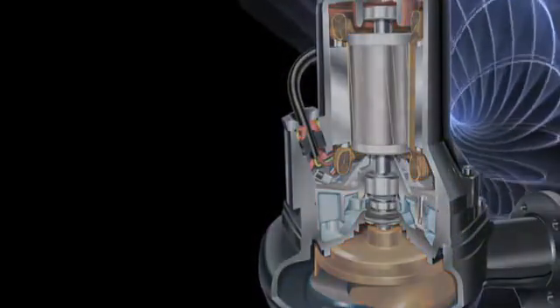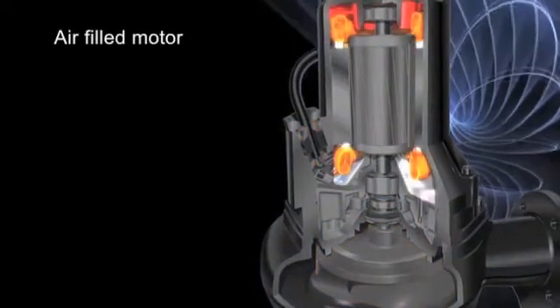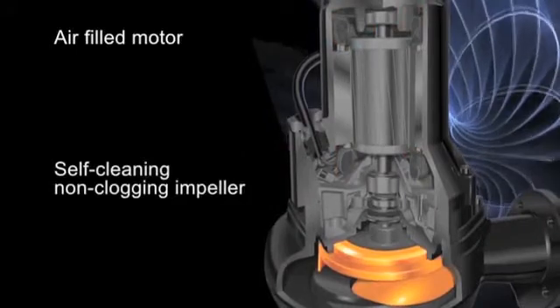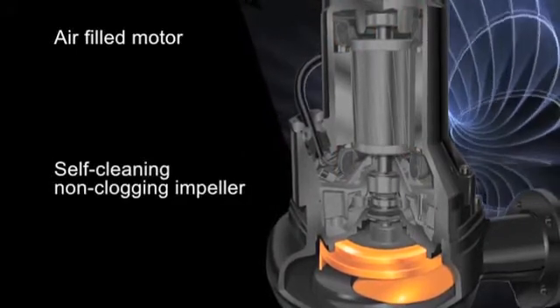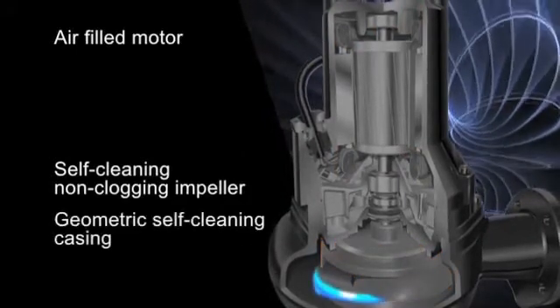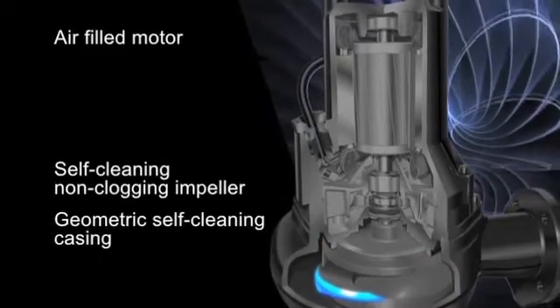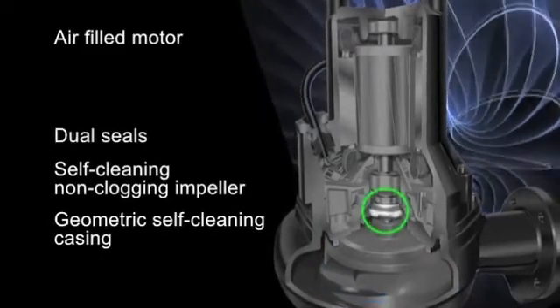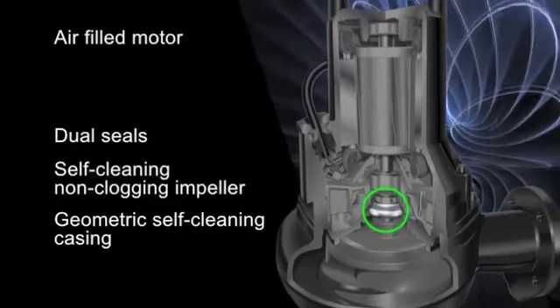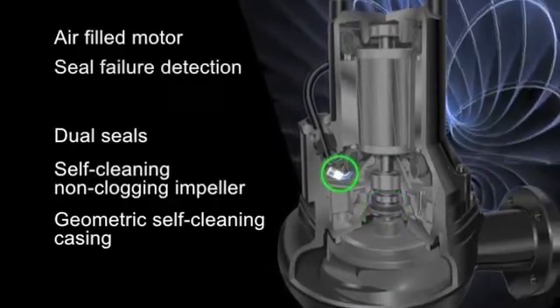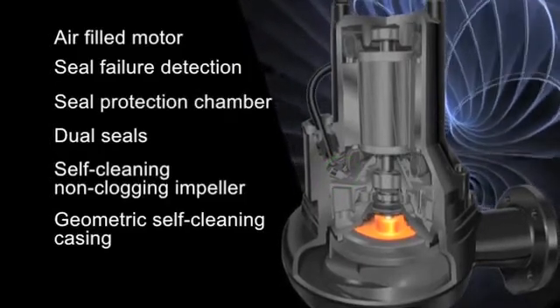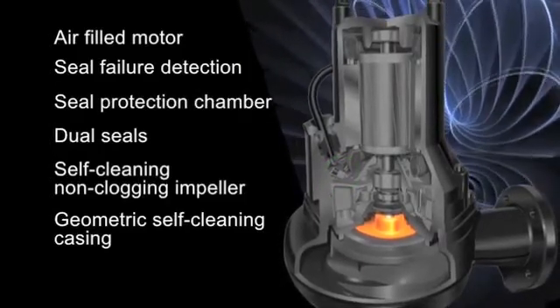From top to bottom, the IMPACT pump is built to get the job done. The air-filled motor improves the pump's overall efficiency. The self-cleaning non-clogging impeller ensures long life and greater reliability. A unique geometric self-cleaning casing design reduces the risk of clogging. Dual mechanical hard-faced seals have a longer life. A float sensing device in the oil chamber detects seal failure. A uniquely designed seal chamber protects the outer mechanical seal from damaging debris.